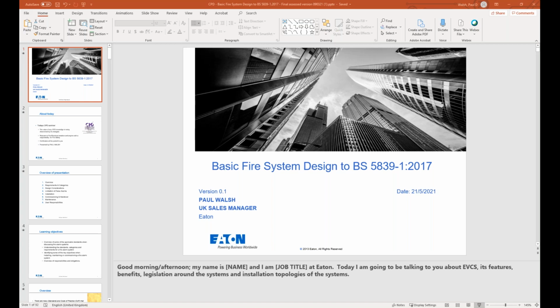Any variations, which I touched on earlier, should also be noted. They can be noted on the installation certificate, they can be noted on the design certificate, but basically they should be noted on the commissioning certificate. So if there are any variations to the system that don't fall in line with the standards, if they're documented, approved and signed off, then it's all good to go and everybody's covered. So if there is any issue further down the line, why wasn't there a detector in a certain place? It's got a journey and a history about it.